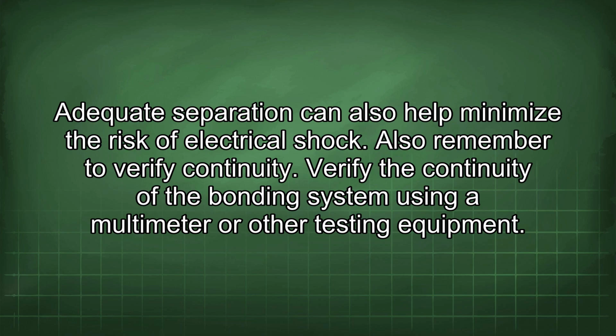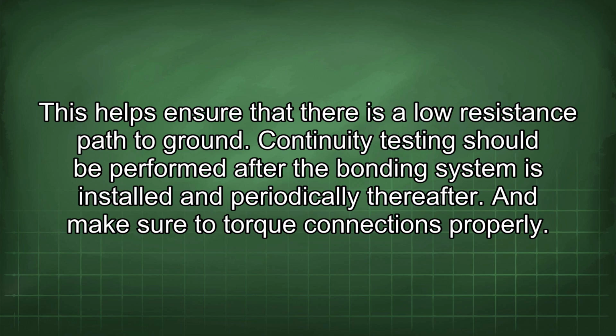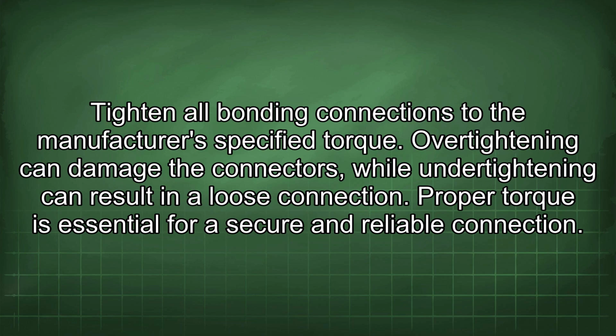Also remember to verify continuity. Verify the continuity of the bonding system using a multimeter or other testing equipment. This helps ensure that there is a low resistance path to ground. Continuity testing should be performed after the bonding system is installed and periodically thereafter, and make sure to torque connections properly. Tighten all bonding connections to the manufacturer's specified torque. Over-tightening can damage the connectors, while under-tightening can result in a loose connection. Proper torque is essential for a secure and reliable connection.